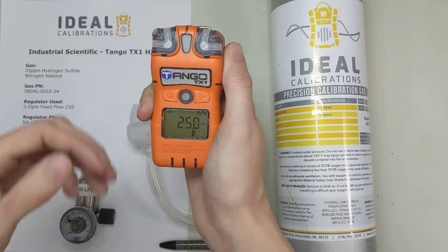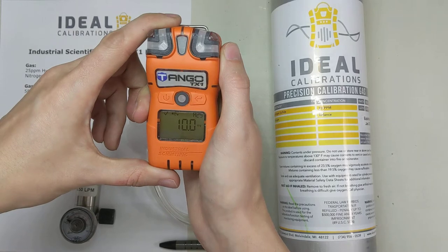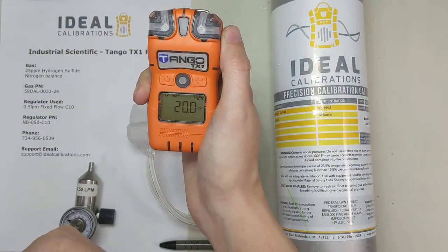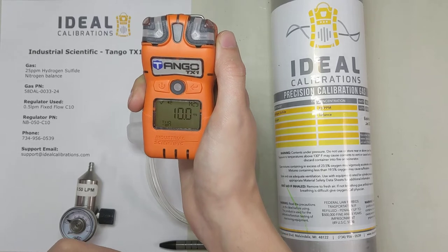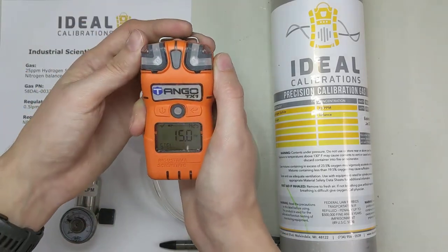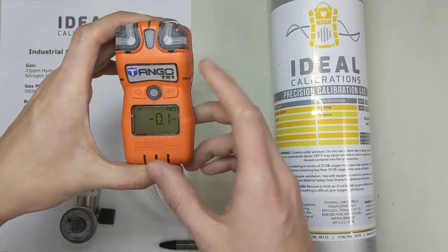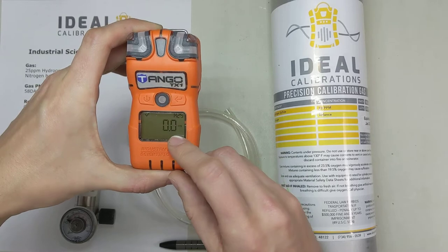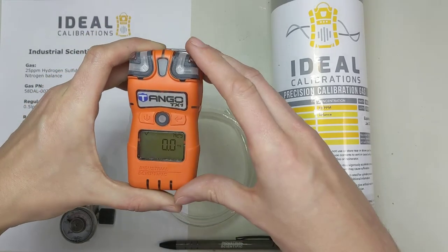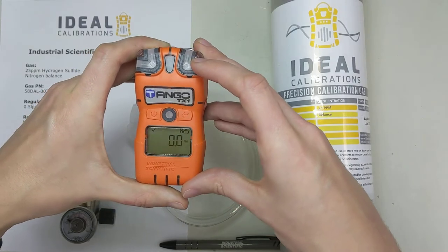It's going to go through a few of the settings — the time, date, things along those lines, as well as your alarm limits, low and high. It'll go through STEL and TWA. If you want to make changes to this, you've got to hook into it through an IR reader on the docking stations — you can get that from ISC. Now we're in normal reading mode. This one's at 0, going to negative 0.1, and it was at 0.2 when we started, so it might just be stabilizing, but it probably needs calibration.